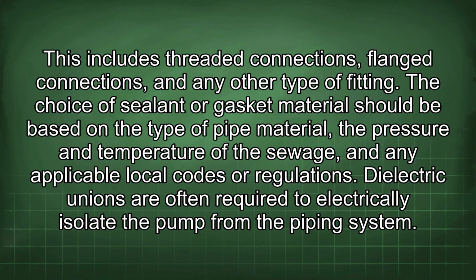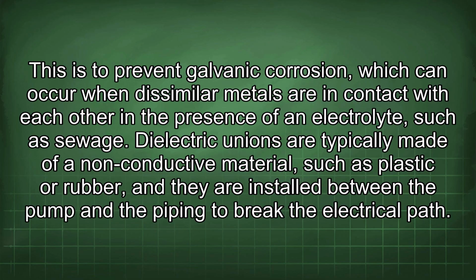Dielectric unions are often required to electrically isolate the pump from the piping system. This is to prevent galvanic corrosion, which can occur when dissimilar metals are in contact with each other in the presence of an electrolyte such as sewage. Dielectric unions are typically made of a non-conductive material, such as plastic or rubber, and they are installed between the pump and the piping to break the electrical path.